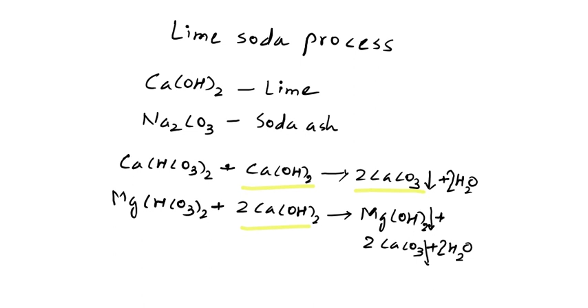Similarly, magnesium bicarbonate, the magnesium temporary hardness, also reacts with lime to give magnesium hydroxide. It also gives calcium carbonate and water. So like that, the calcium and magnesium temporary hardness is removed by using the lime. You can see that lime reacts with calcium bicarbonate to give calcium carbonate, and lime reacts with magnesium bicarbonate to give magnesium hydroxide and calcium carbonate. Both of these settle down.